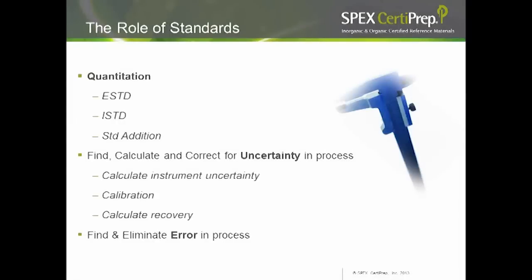There are quite a few roles for standards. The one most familiar to analysts is quantitation — using standards as an external standard, an internal standard, or for standard addition. Standards can also be used to find, calculate, and correct for uncertainty in your process, such as calibration of your instrument, instrument uncertainty, and calculation of recoveries. They can also be used to find and eliminate error in your process; by running standards throughout your process, you can monitor and identify any potential sources of error.